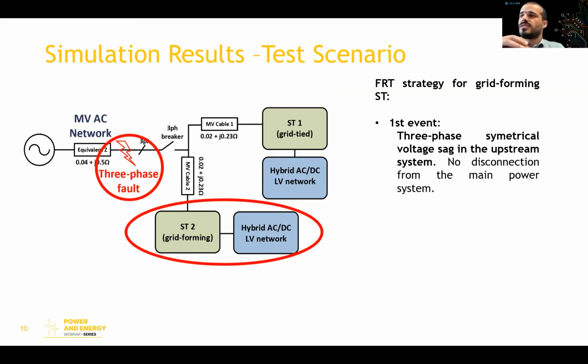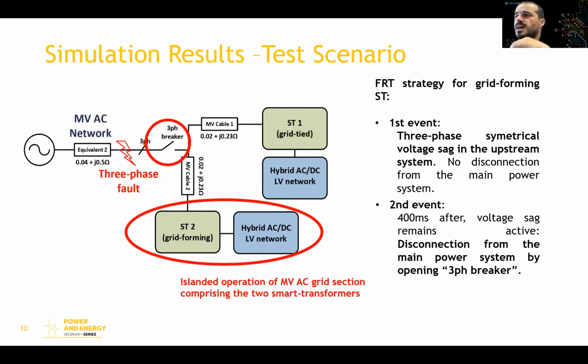For the evaluation of the fault ride-through strategy for the grid forming, two phases were considered. In the first phase, a three-phase symmetrical voltage sag in the upstream system occurs, and there is no disconnection from the main power system. But after 400 milliseconds, the voltage sag remains active and the three-phase breaker is opened, in order to allow the grid-forming smart transformer to support the medium voltage grid in island mode.